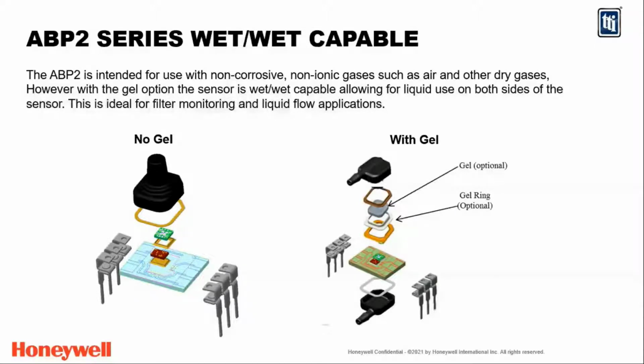Well, what happens if you don't cover the wire bonds and you put liquid in there? The sensor's going to fail, right? So having that visual check is important. Very few competitors do that. They do a blind fill, and then you don't know if everything's covered or not. They just throw some gel in at the very end. They inject some gel, and hopefully things are covered, but they don't really have any way of knowing if they are or not until you put liquid on it, and then potentially it's too late. So that's an improvement.